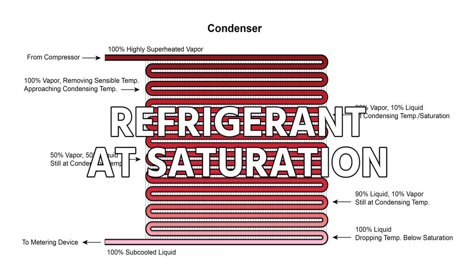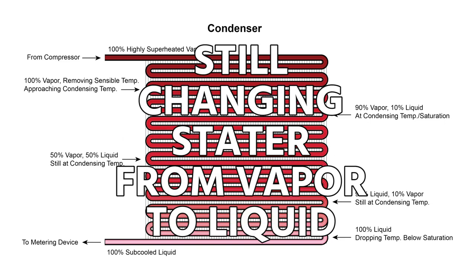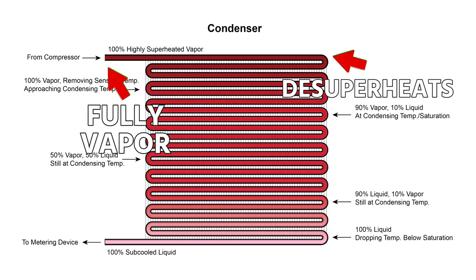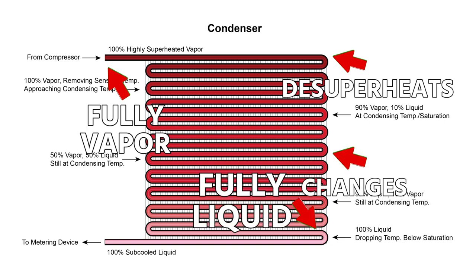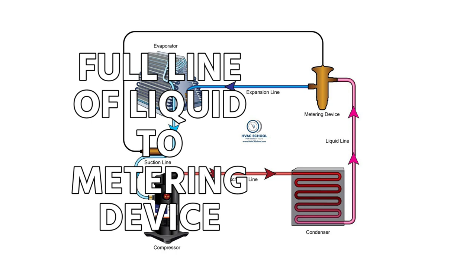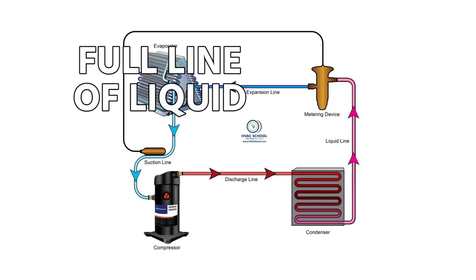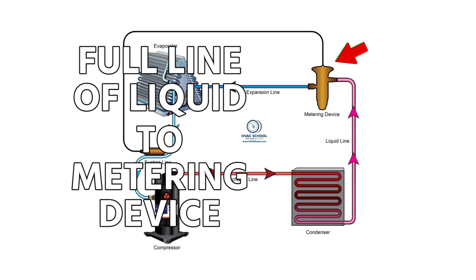When your refrigerant is at saturation, that means it's still changing state from vapor to liquid. So it starts off fully vapor, it desuperheats, and then it goes into this phase where it's changing. Once it drops below that, now we know that it is fully liquid. Our goal is to deliver a complete column of liquid to our metering device, which is why you're generally going to see around 10 degrees of subcool. Following manufacturer specifications, around 10 degrees of subcooling ensures that we're going to deliver a full line of liquid to our metering device on our liquid line.